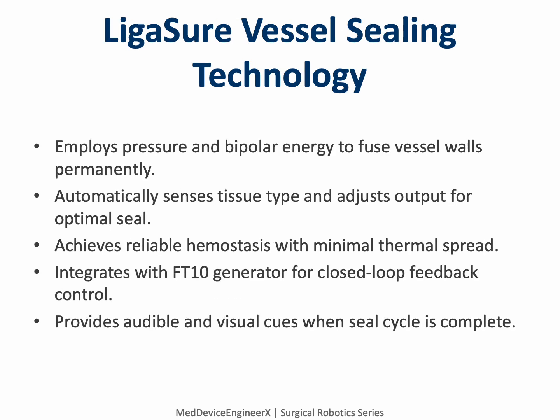LigaSure technology revolutionized electrosurgical sealing by combining energy and pressure under precise control. It works through bipolar jaws that grasp tissue while the generator modulates current flow. Sensors measure tissue impedance continuously, allowing the FT10 to adjust power and duration in milliseconds. The result is a uniform seal, strong enough to withstand 3 times normal vessel pressure with minimal collateral heat.